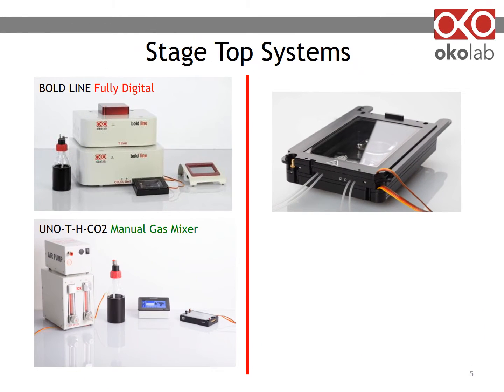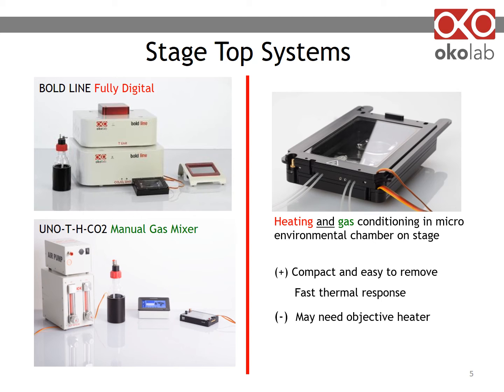All Okolab stagetop chambers are compatible with both types of controllers — bold-line and UNO THCO2. The stagetop chamber provides both heating and gas conditioning. Our easy-to-remove chambers have a fast thermal response. Remember to use an objective heater if you're imaging with oil-immersion objectives.